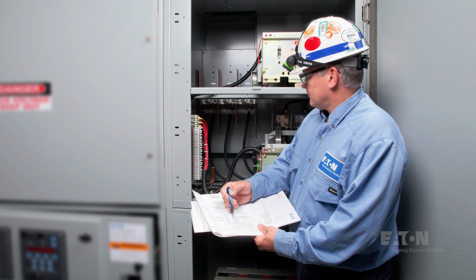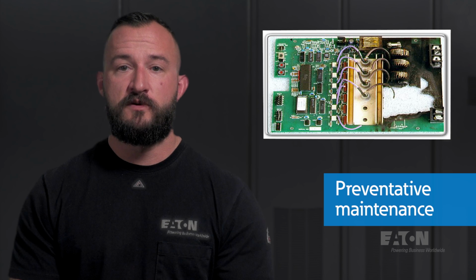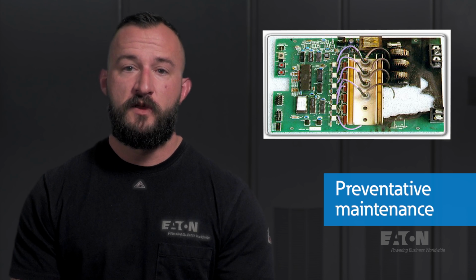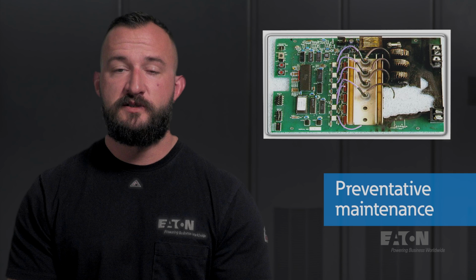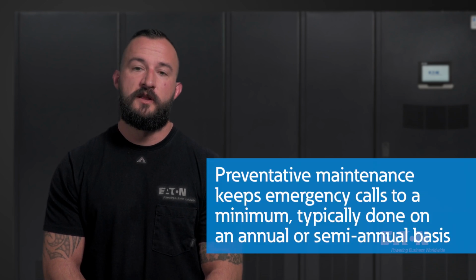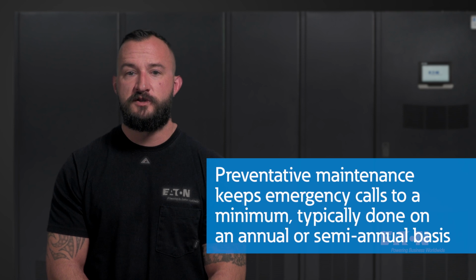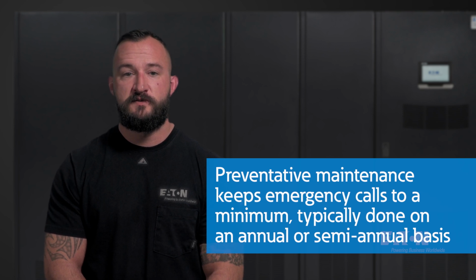Unplanned outages or issues are a thousand times worse than planned outages or downtime. In most cases, with redundancy, we can do preventive maintenance on equipment without any disruption to the loads. Preventive maintenance accounts for about 70% of our time and allows the field team to keep emergency calls to a minimum and prevents field issues.